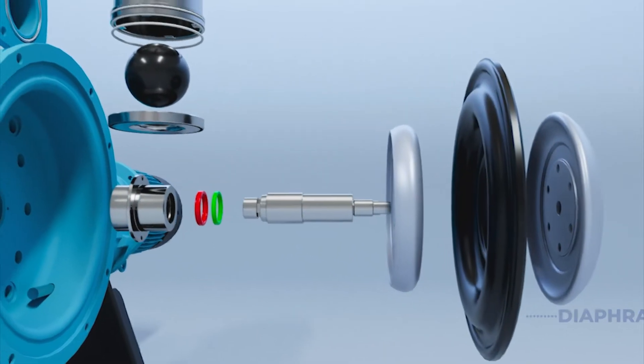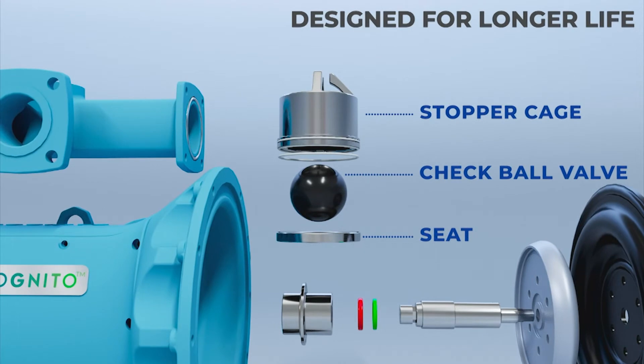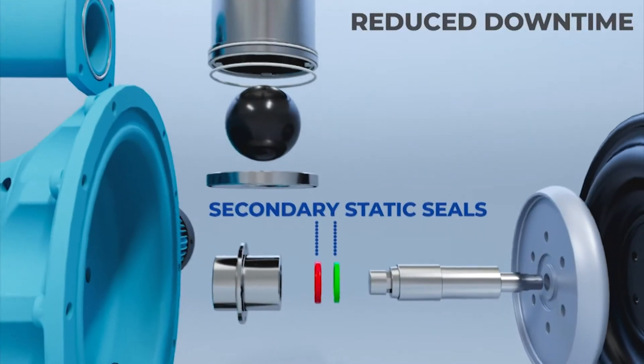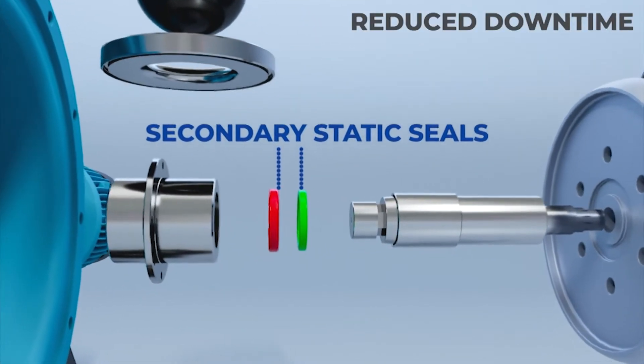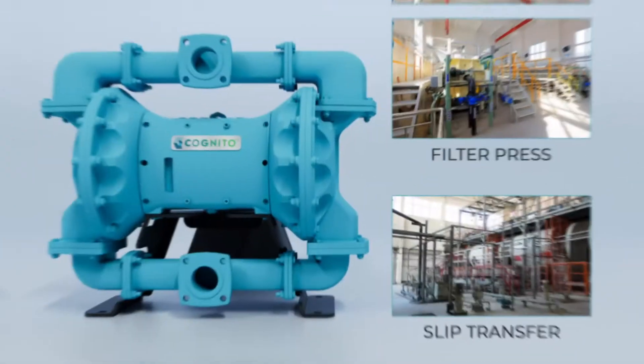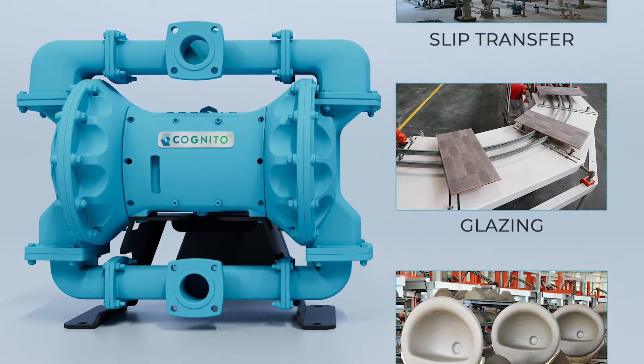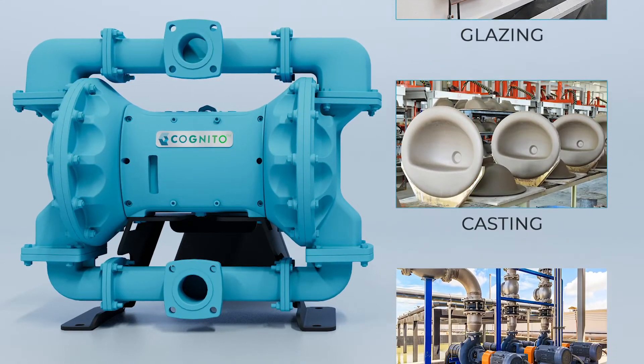The designed seat and stopper cage arrangement increase the life of manifolds and seats. Secondary static seals eliminate the direct contact with the fluid and this helps to protect the pump mechanism in case of diaphragm failure. It is most suitable for a wide range of viscous and abrasive fluids and can be used across multiple industries.